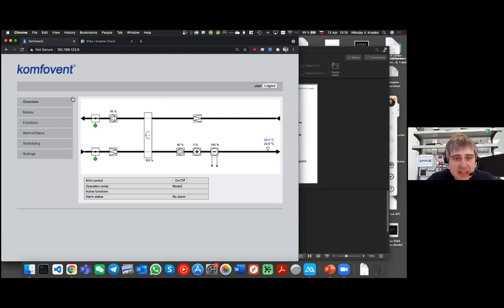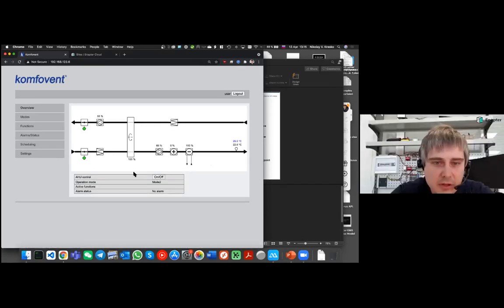Here we can see the P&ID of this device. The top vent line shows the exhaust line from the house through the filter, through the rotary heat exchanger, through the fan—running at 55%—through the damper, out to the street. The bottom vent line shows the intake air, coming through the damper, filter, then the rotary heat exchanger, the fan running at 65%, then an electric preheater, the chiller, and into the house.